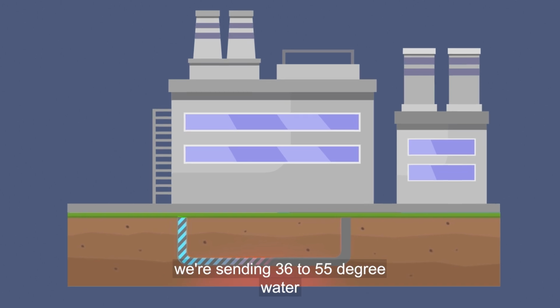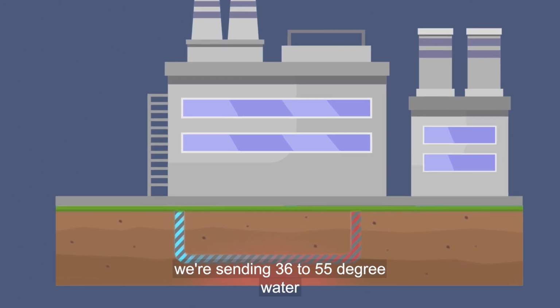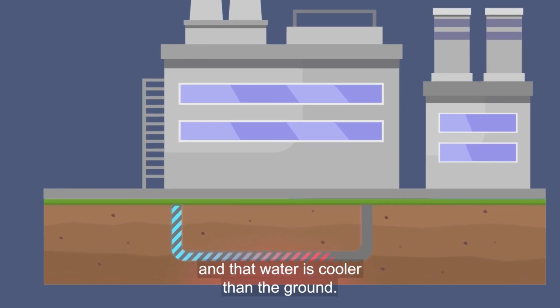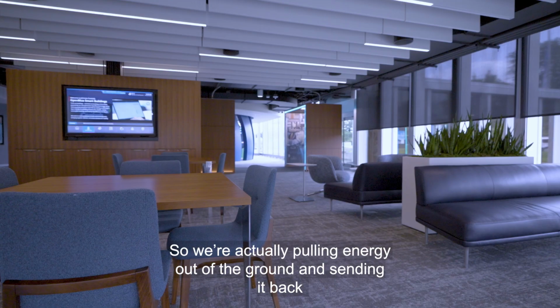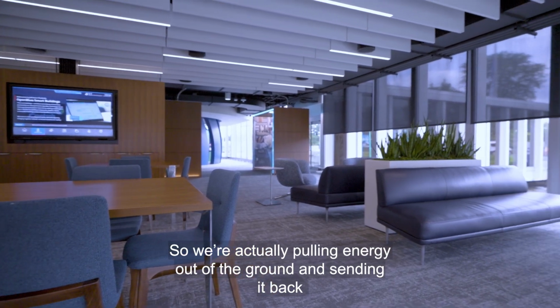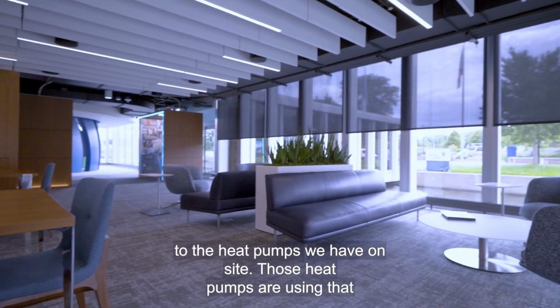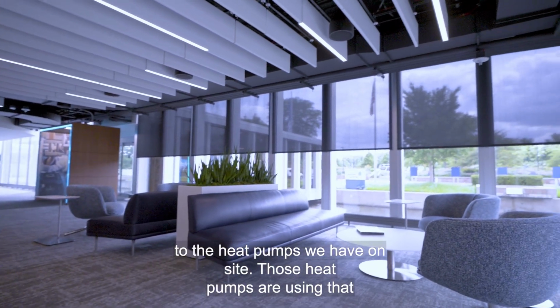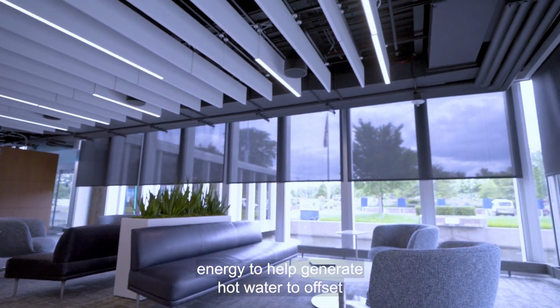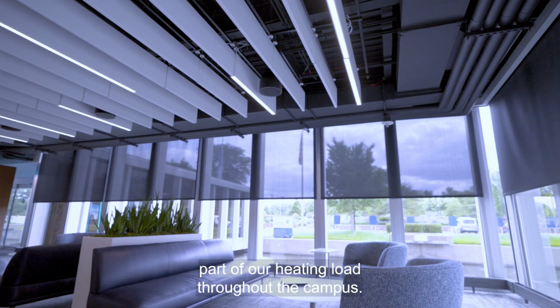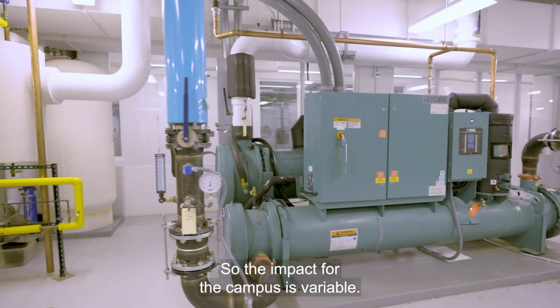Throughout the cooler months, we're sending 36 to 55 degree water through the pipes in the ground, and that water is cooler than the ground, so we're actually pulling energy out of the ground and sending it back to the heat pumps we have here on site. Those heat pumps are using that energy to help generate hot water to offset part of our heating load throughout the campus. So the impact for the campus is variable.